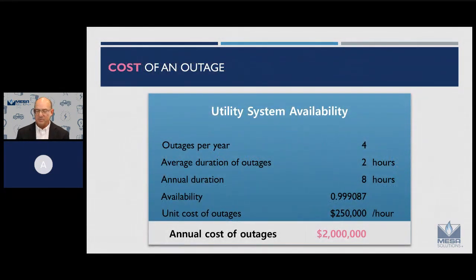So in our simple example, we'll talk about a utility system availability where suppose your utility at this location has 4 outages per year, and the average duration of each outage is 2 hours. That gives you a total of 8 hours, and just calculating the ratio of outages to overall uptime, it gives you an availability of 0.999087 in that case. So 3 nines of availability.